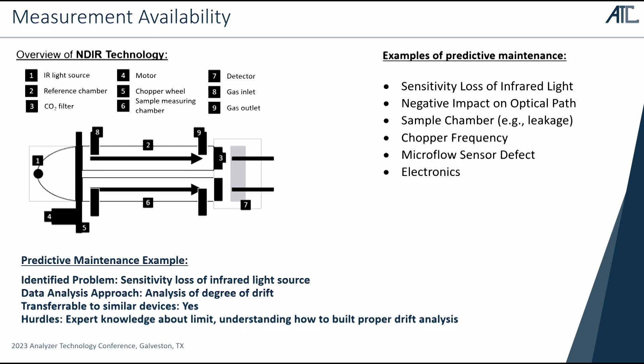But if the drift was increasing, that was a sign for us, at a specific speed, that we now have to react, and a user has to get the information quite soon that he needs to replace the infrared light source. So that was a really good approach there, and this statistical rule is transferable to any kind of other device as well.